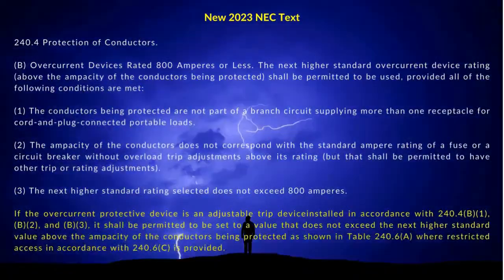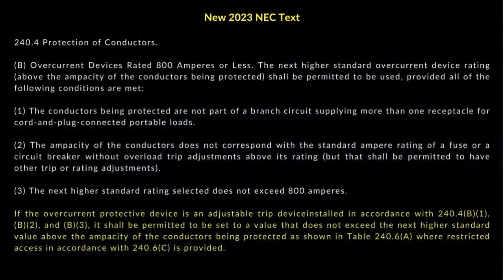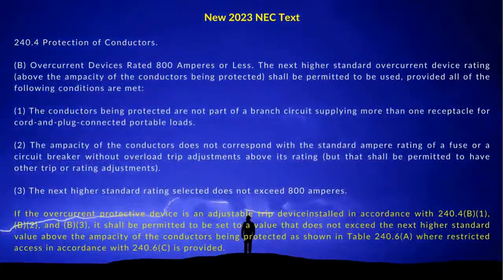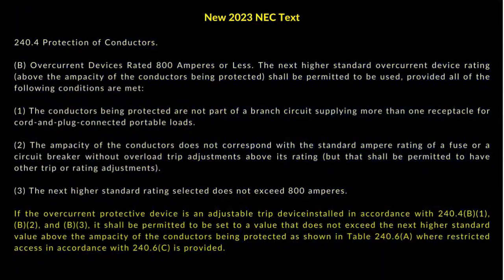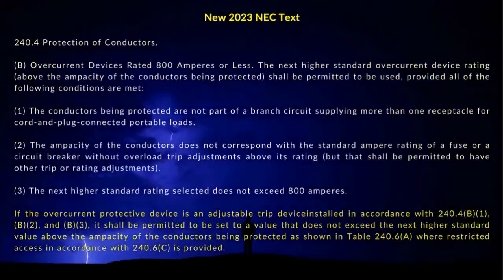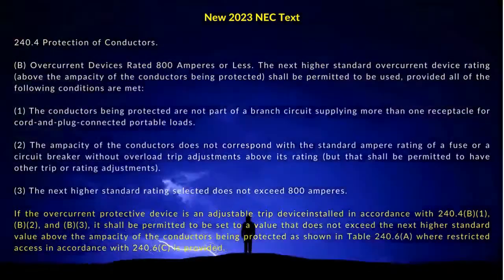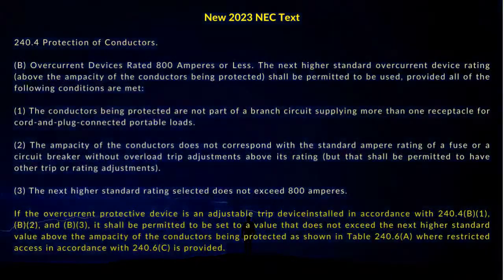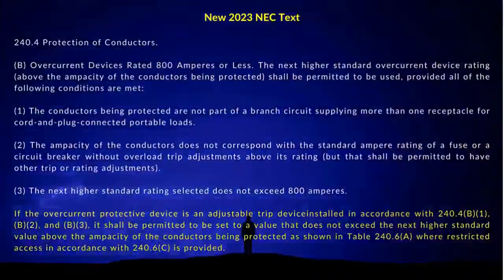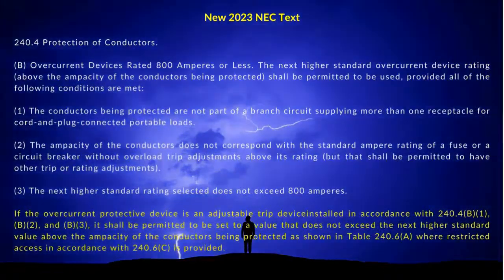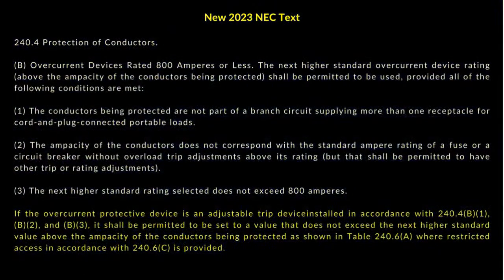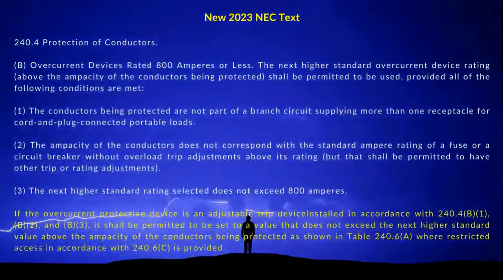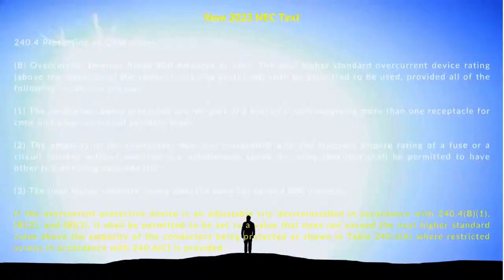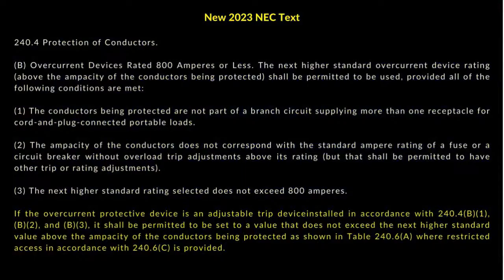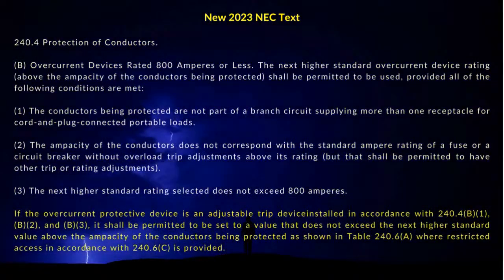A new paragraph has been added to 240.4b that states, the next, higher standard overcurrent device rating, above the ampacity, of the conductors, being protected, shall be permitted, to be used, provided, all of the following conditions, are met. Subdivision B1, states that, the conductors, being protected, are not part of, a branch circuit, supplying, more than one receptacle, for cord and plug connected, portable loads. Subdivision B2, states that, the ampacity, of the conductors, does not correspond, with the standard ampere rating, of a fuse or a circuit breaker, without overload trip adjustments, above its rating, but, that shall be permitted, to have other trip, or rating adjustments. Subdivision B3, the next higher, standard rating selected, does not exceed, 800 amperes.